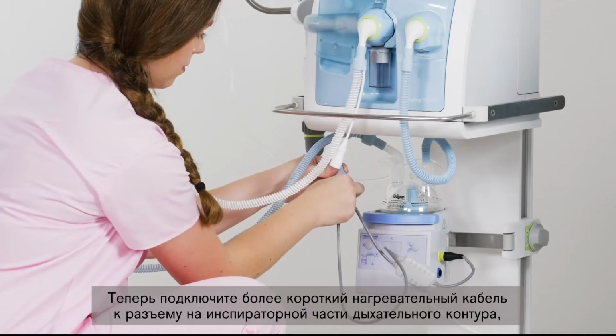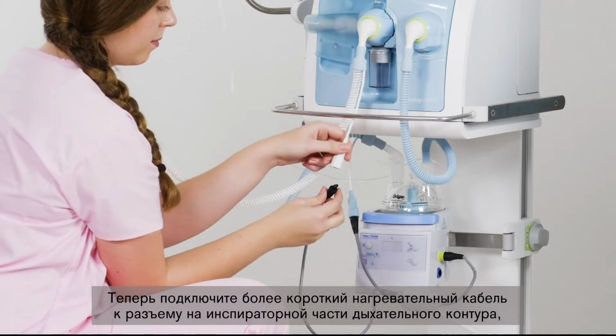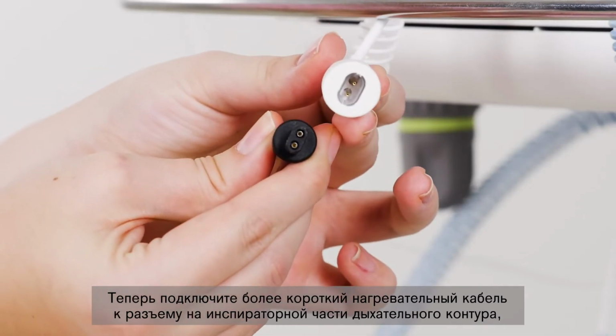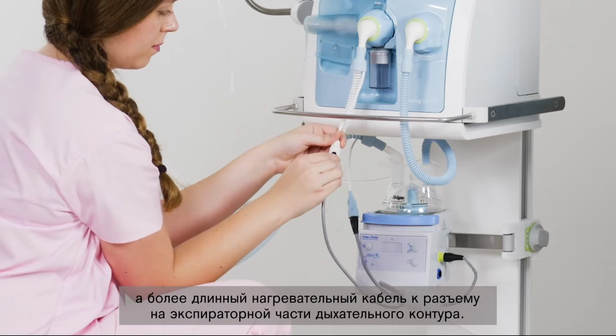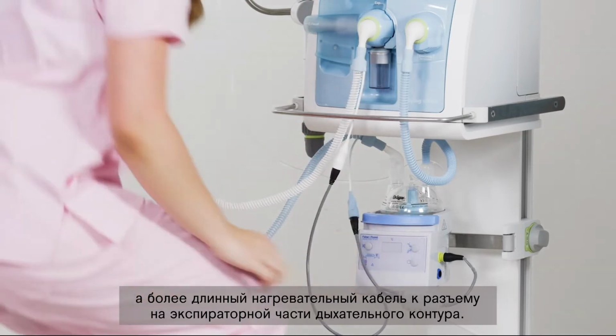Now connect the shorter heating cable to the connector on the inspiratory limb of the breathing circuit, and the longer heating cable to the connector on the expiratory limb of the breathing circuit.